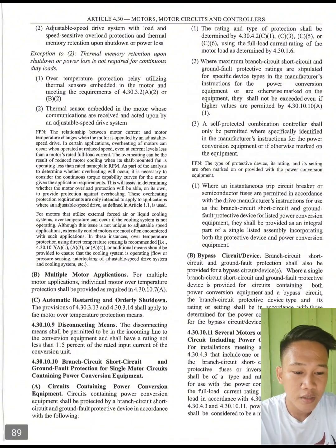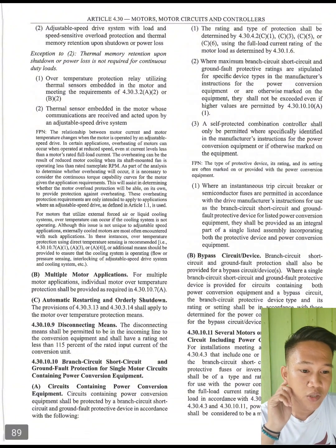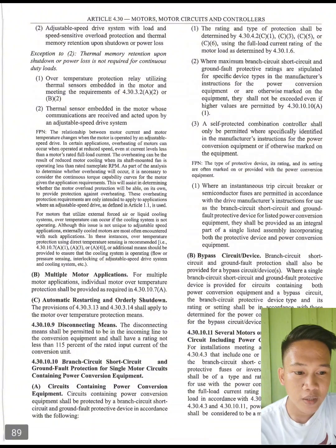So, next, a self-protected combination controller shall only be permitted where specifically identified in the manufacturer's instructions for the power conversion equipment or if otherwise marked on the equipment. Where an instantaneous trip circuit breaker or semiconductor fuses are permitted in accordance with the drive manufacturer's instruction for use as the branch circuit, short circuit, and ground fault protective device for listed power conversion equipment, these shall be provided as an integral part of a single listed assembly incorporating both the protective device and power conversion equipment.